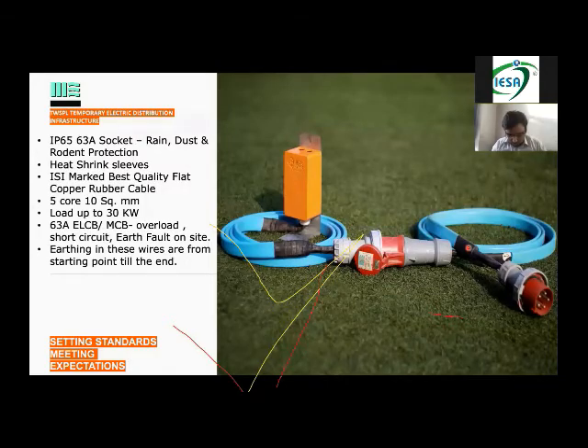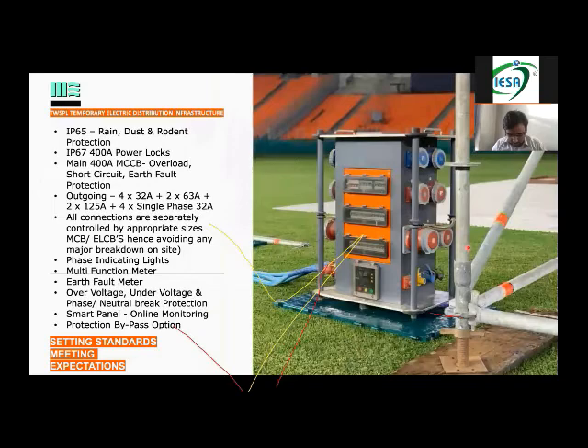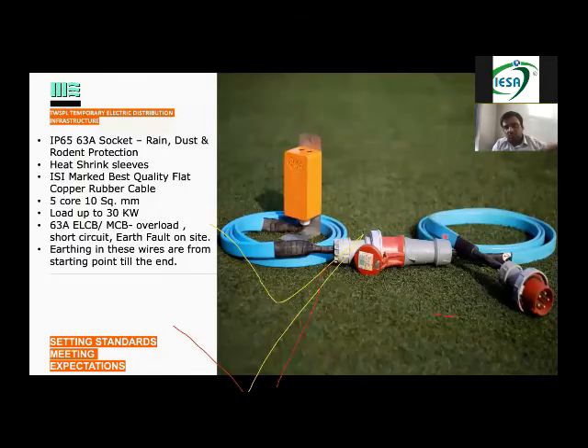So from the genset or maybe from the house power, we take the power, it comes inside this box. This socket, maybe there's a 63 amp. We put our flat cable inside this, and at the end point, we tell the exhibitor, please connect your wires in these 2 holes only. They have to be separate also.